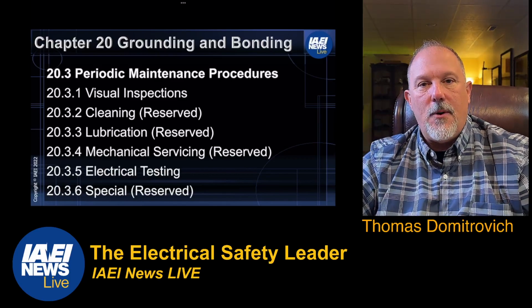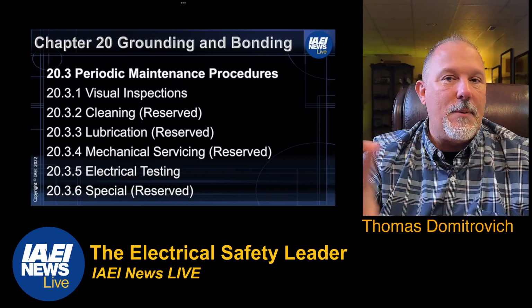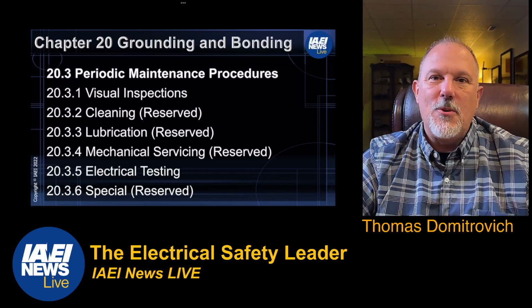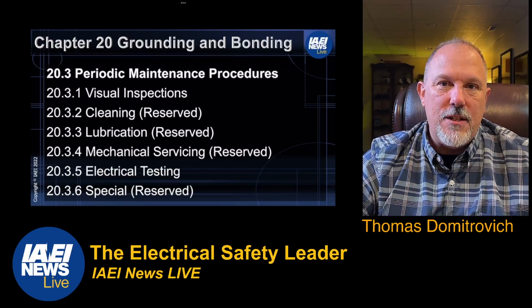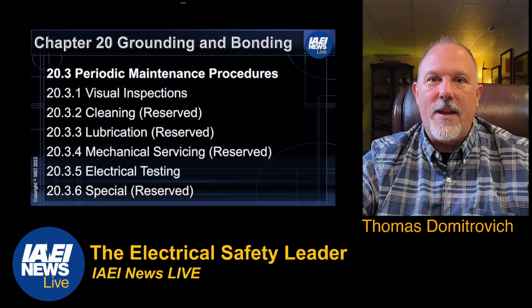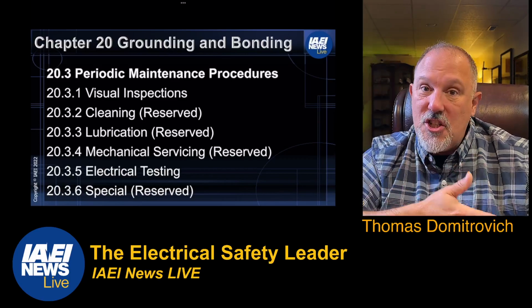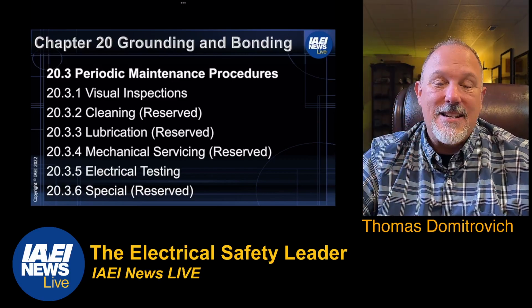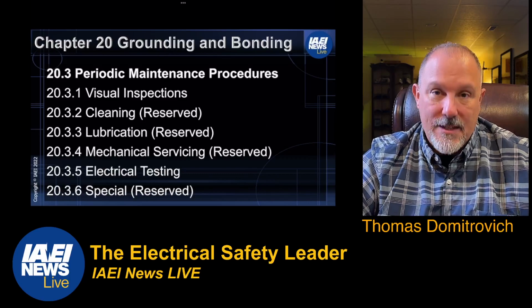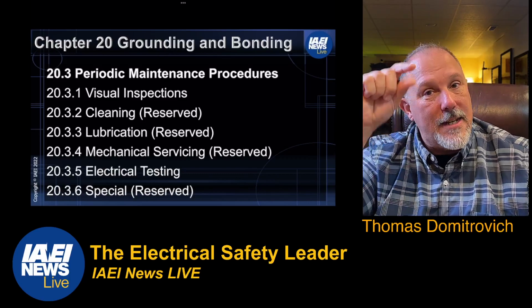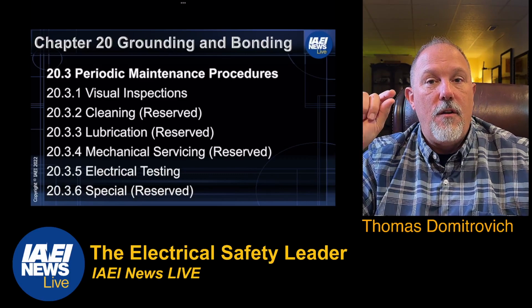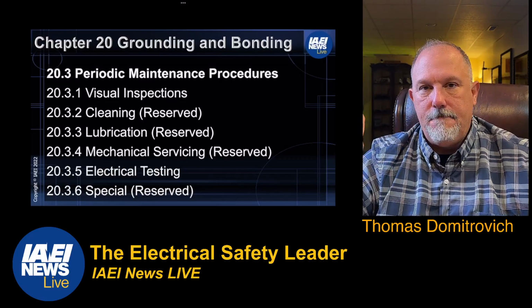So grounding and bonding applies to any piece of equipment: panel board, switchboard, switchgear, switches, industrial control panels, electric machinery, anything connected to the power distribution system that has instructions and maintenance. Take a look in each of those components for any guidance on grounding and bonding.